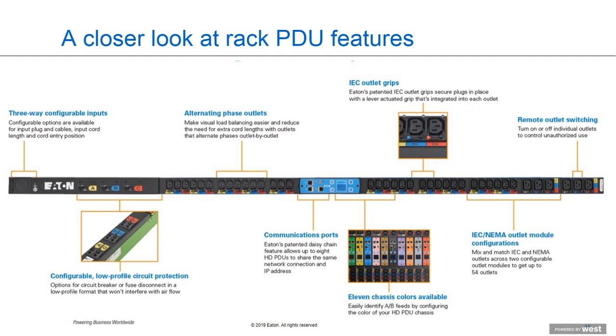We talked a little bit about phase balancing, so having alternating phase outlets that are color coded. As you go up and down that PDU, you want to move between phases and branch circuits so you can help load balance everything. This keeps your devices evenly balanced across all your circuit breakers and evenly balanced across all your phases.